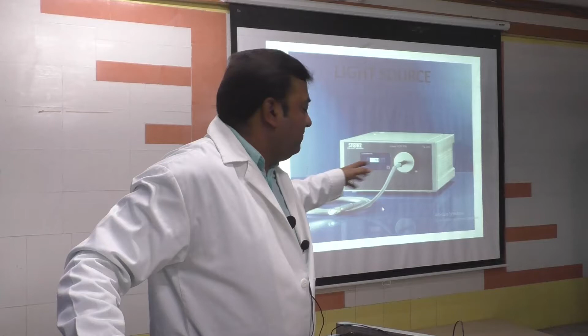And then the light source, because unless you have a light source, the camera cannot capture an image. So when you take a photo with your mobile or whatever, you need light. If light is not there, you will be putting in artificial light. So similarly here, the inside of the abdomen is not self-luminous. So you need a light source. You have another tubing for the light source. This tubing will be connected again to this laparoscope, and whatever light is there goes into the abdomen.